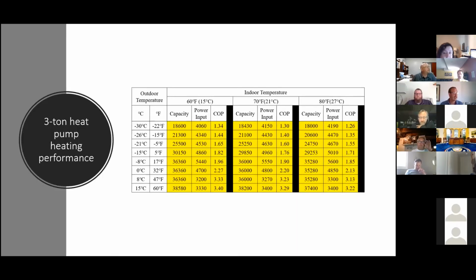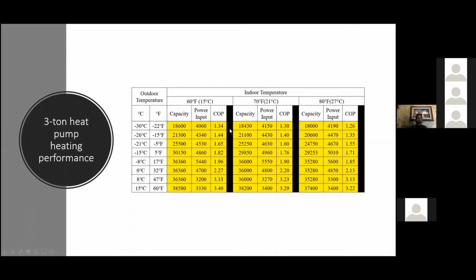What's interesting about this data table is it goes from 60 all the way down to minus 22 for the outdoor temperature. So when you look at a heat pump ratings table, same. This looks the same for VRF. We're going to look at the temperature, we're going to look at the output. So this 3-ton, 36,000 BTU per hour unit can produce half the heat compared to the rating, but it's at minus 22. So yes, the unit derates. It's still more efficient than electricity, but we just don't have a lot of bin hours here at minus 22. And we're going to get into a little bit more detail on that as we go along.